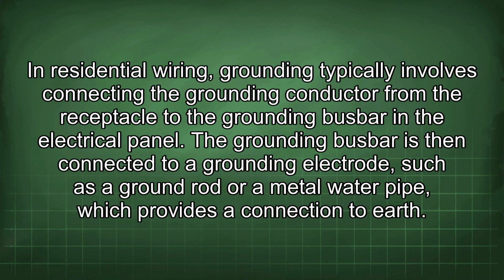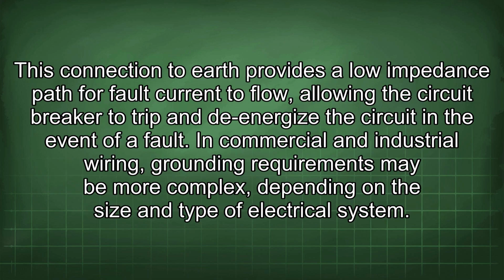In residential wiring, grounding typically involves connecting the grounding conductor from the receptacle to the grounding busbar in the electrical panel. The grounding busbar is then connected to a grounding electrode, such as a ground rod or a metal water pipe, which provides a connection to earth. This connection to earth provides a lower impedance path for fault current to flow, allowing the circuit breaker to trip and de-energize the circuit in the event of a fault.